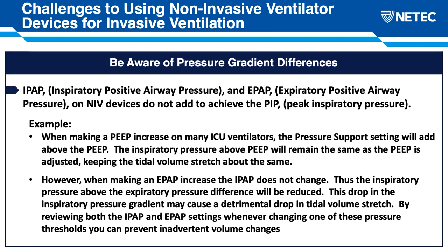One of the other things to be aware of is the pressure gradient differences on your non-invasive device, your IPAP and EPAP, versus a traditional ICU ventilator that most of us get used to. With the majority of ICU ventilators, when you adjust your PEEP, your pressure above the PEEP goes up with it. So in other words, your delivered volume, or the stretch delivered, is about the same. The example would be your IPAP and EPAP on a non-invasive device. They don't follow each other. They are set separately.